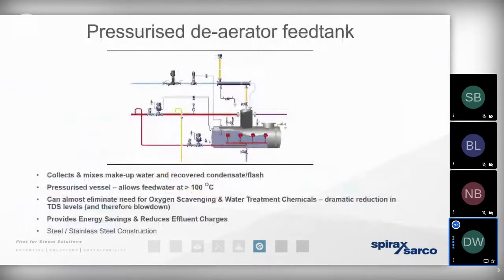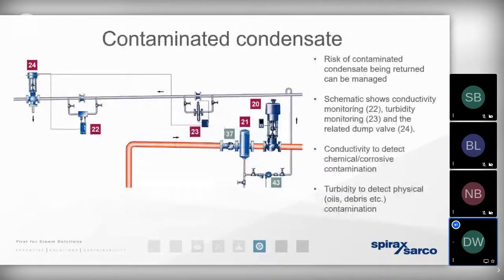So other ways that we can increase the rate of condensate return is by using a pressurized deaerator. We'll talk about the PDA in a little bit more detail in future weeks. But by keeping the hot well under pressure, let's say 0.2 bar gauge, it means we can elevate the temperature of the feed water beyond 85 degrees. And that can't really be improved on with traditional vented systems, because of the risk of cavitation. But if we've got that hot water under pressure, it means we can contain more and more of those flash steam losses. And it means that we can really start to quantify the benefits that we can bring to a well-designed steam distribution network.